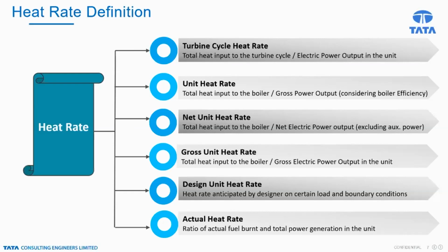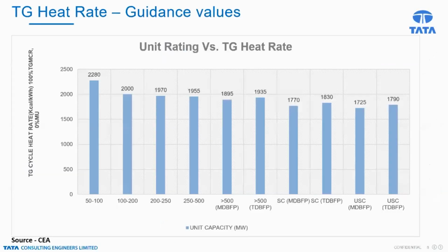Another way is design heat rate versus actual heat rate. Design heat rate is the one which is guaranteed by the supplier or manufacturer based on the design conditions and certain design parameters. And actual heat rate is based on the actual amount of fuel that is burnt in the boiler and the total power generation in actual operating cases. So these are the various definitions of heat rate. Predominantly, we talk about turbine cycle and unit heat rate at the gross level. That is the more prevalent definition.